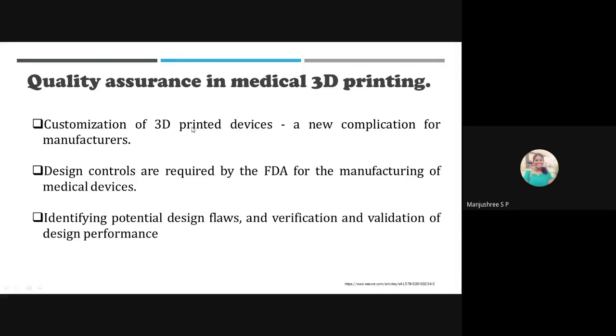And coming to the validation part of your 3D printed medical device, one inherent challenge is making patient-matched devices, with all the steps in conversion of the image file performed every time a device is created, but then the specifications of each device are unique. So in other words, the critical attributes for the specific device and the efficacy criteria of the final device must be validated as part of the software workflow in order to ensure the performance of the finished device for that particular patient. So this is a major challenge to meet the quality assurance.